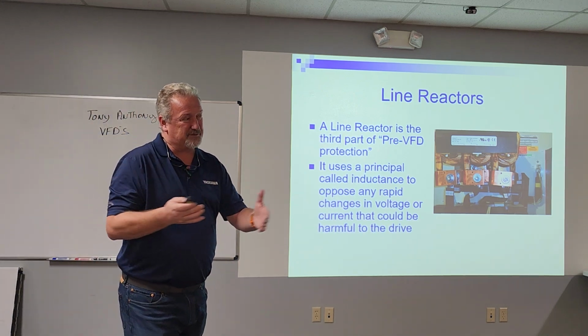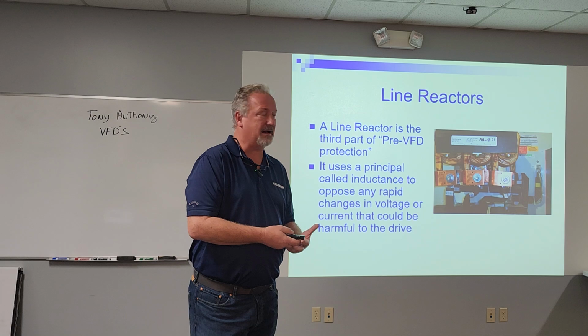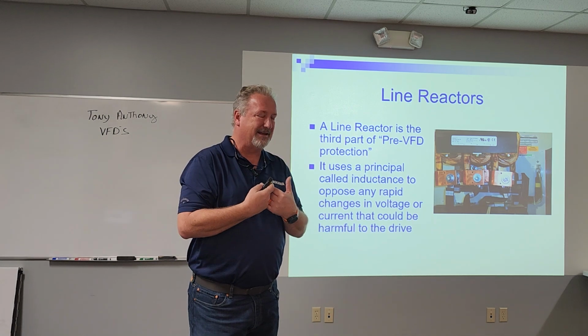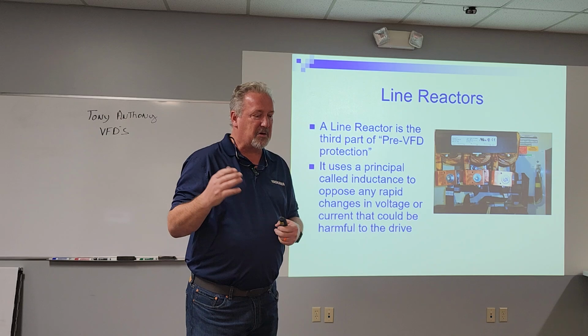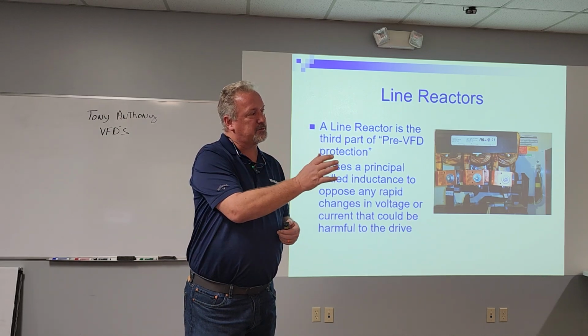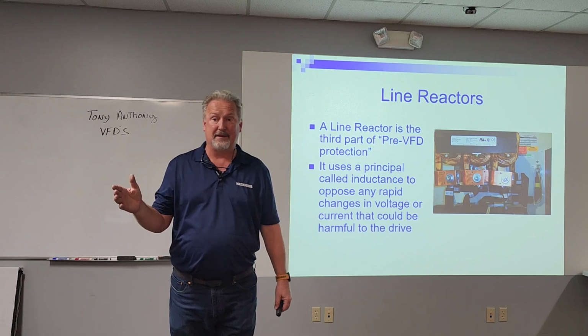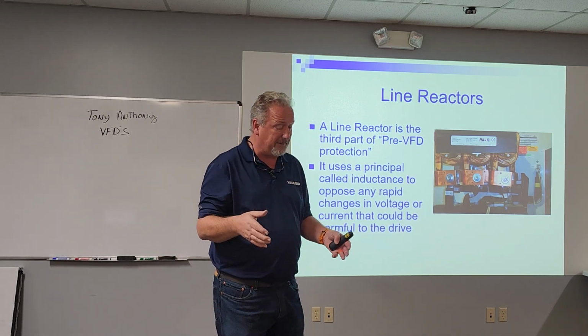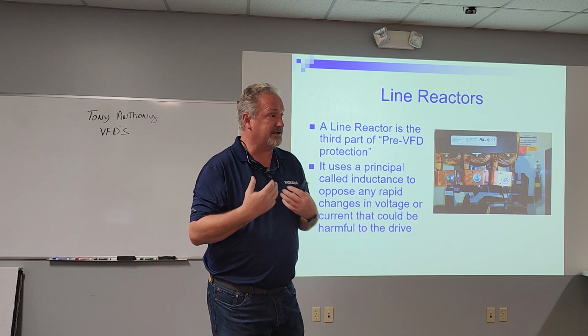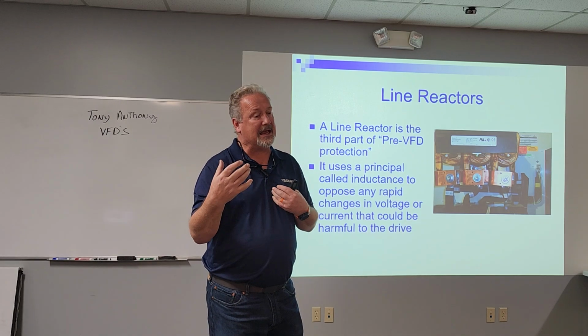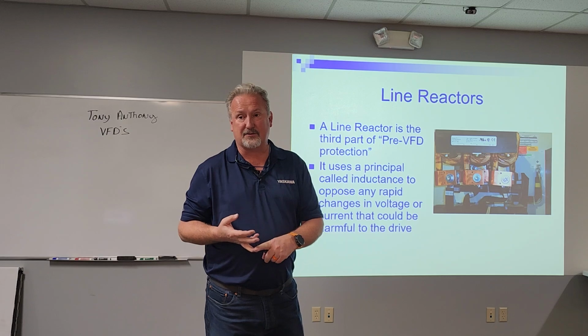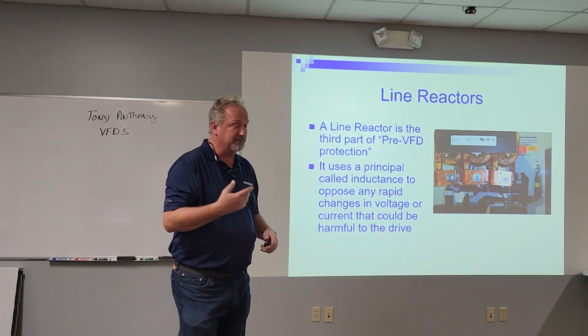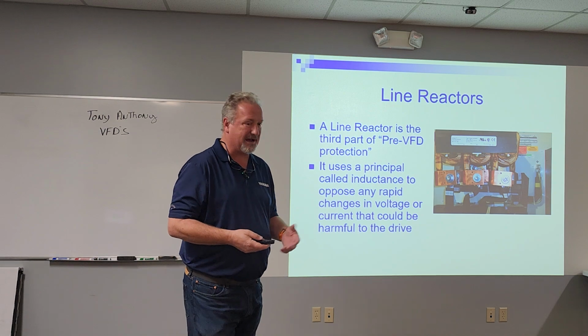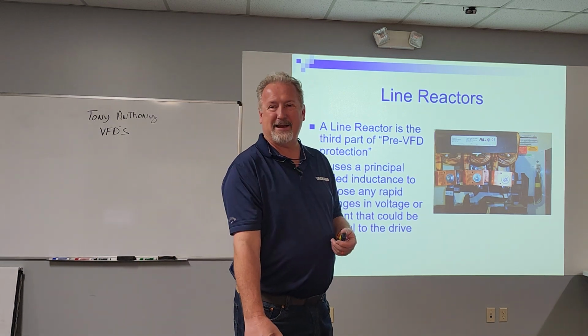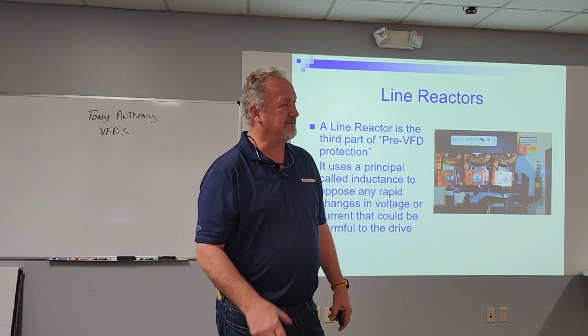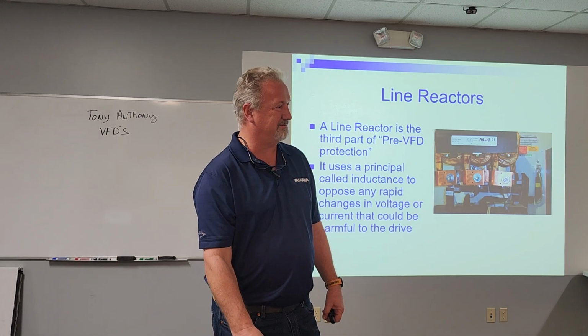If you get enough drives in a building, normally the transformer feeding the drives will basically absorb it and fix it. But it's additive. If you get enough distortion, enough drives, and we're all adding drives to more and more buildings, the transformer can't handle it anymore. It'll start to overheat, and you may have sensitive electronic equipment start to fail. One of my distributors has a good way to describe this. He says, you ever been at a gas station pumping gas and the guy beside you is topping off his tank? You can feel those pulses in your hose, even though you're just pumping straight.